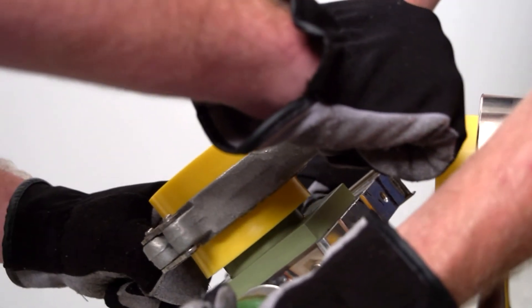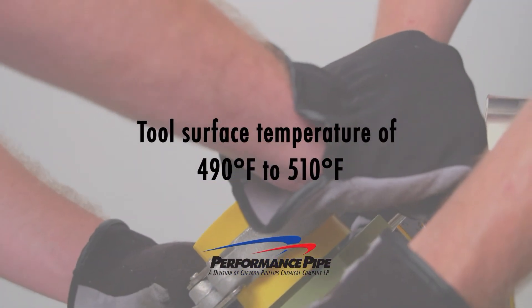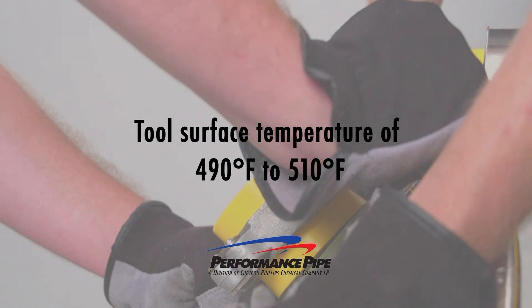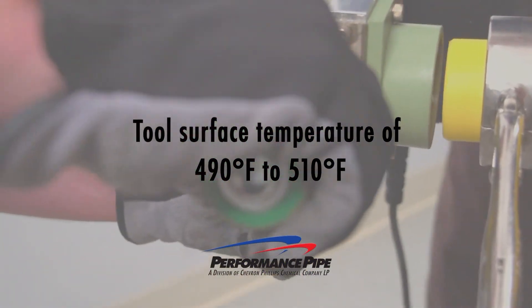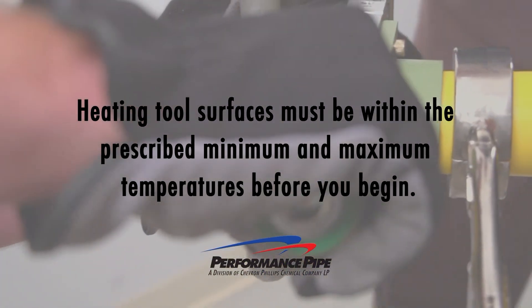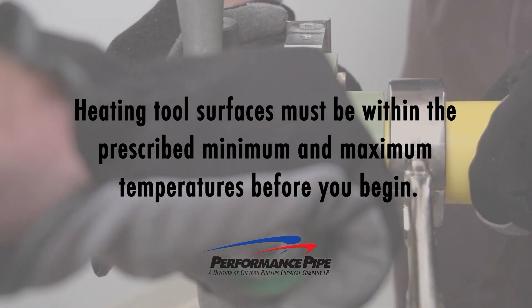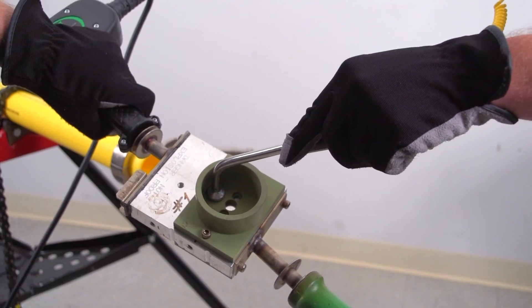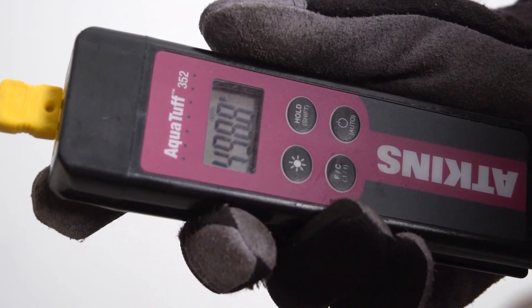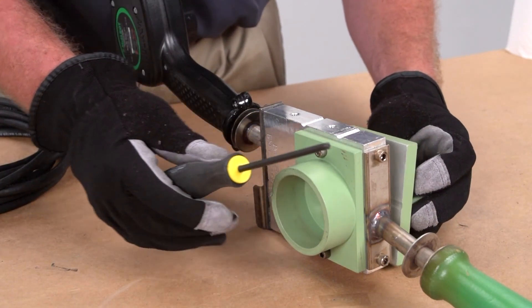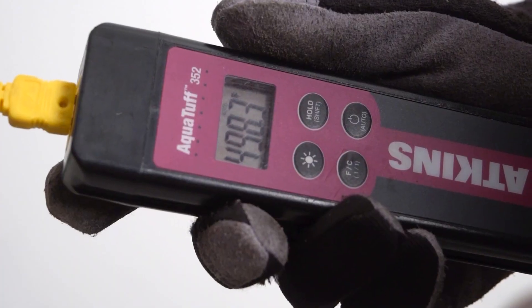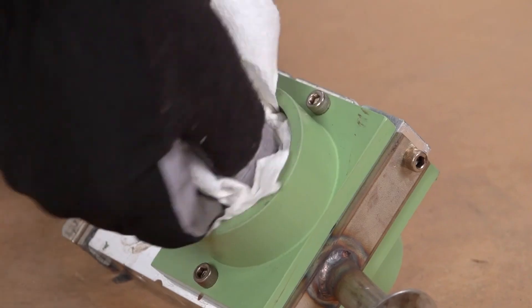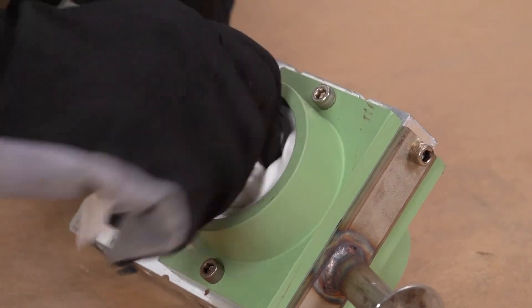Performance Pipe recommends the following heating tool surface temperature. Where heating tool surfaces will contact the pipe or the fitting, all points on both heating tool surfaces must be within the prescribed minimum and maximum temperatures before you begin. Use a pyrometer to verify the actual surface temperature. Install the correct faces on the heating tool and heat to the correct surface temperature. The male and female socket faces on the heating tool must be clean.